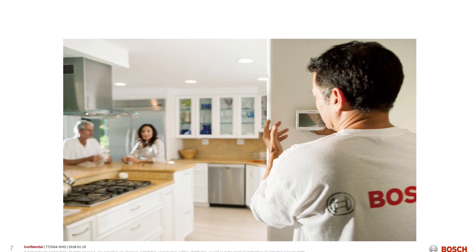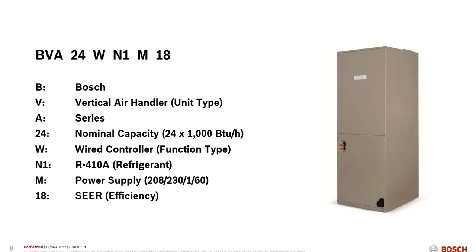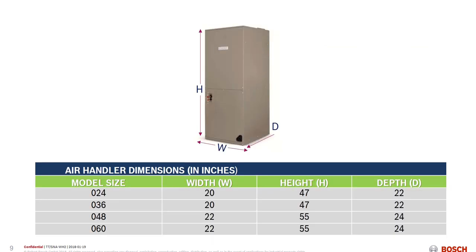Let's talk about the installation process. Here's my unit. It's a BVA 24. So we have 4 multi-position one-piece air handlers: the 24, 36, the 48, and the 60. In this particular application, it's upflow. You see that it is a 410A, and it's got a 410A expansion valve already installed in the coil. It is a 230 volt single phase air handling device. Inside this device has an X13 style blower motor. Basically what we would say is a 5-speed. You choose 3 of those speeds.